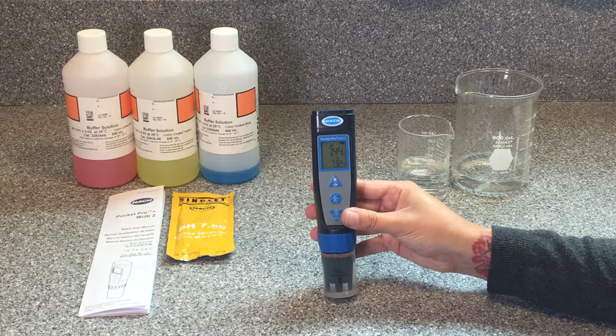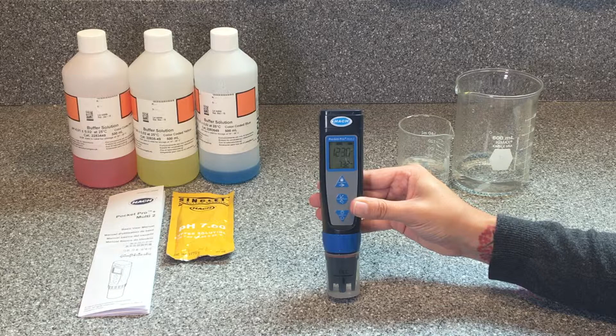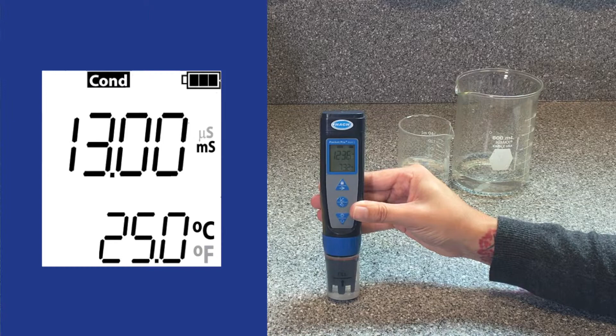So we're going to hold this top button to move to the next parameter, which is conductivity, which again is indicated at the top of the screen. As you can see, it takes a second for the reading to stabilize. That means that it may drift for a minute. Always wait until it stops drifting or that it stabilizes before you actually write down the reading. If it continues to bounce back and forth between two numbers, write down the average of the readings. And again, pay attention to units. Conductivity may be shown in microsiemens per centimeter, which is indicated here, or it may be shown in millisiemens per centimeter, which would be indicated by an ms.